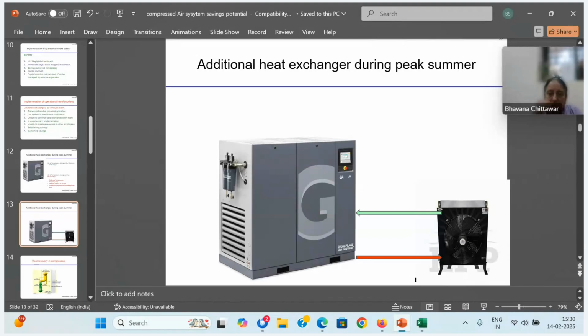Clients. In fact, I want all compressors to keep the heat exchangers outside, not inside the compressor room. We have to get the water-cooled compressor, and they keep the closed-loop cooling tower or radiator, whatever you call it, outside. There's no water consumption. You can run it filled with coolant like a car. This will reduce the air oil temperature inside the room, the ambient conditions in the room. Your energy consumption will come down drastically. Performance will improve. You can reduce the oil changing frequency. In reverse, you can increase the oil life, and this will save a lot. In fact, you can retrofit existing compressors also.